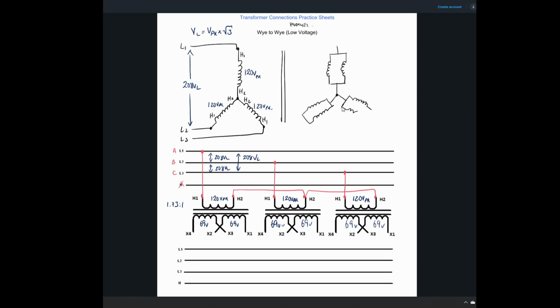I've seen them on solar panel installs where the solar panel output is 277/480 and they want to change that to 120/208, so they'll use a Y to Y transformer. In some machinery or in some installs, you will see a Y to Y connection. The issue with Y to Y transformers, from what I've read, is that harmonics can pass between the primary and secondaries because they have that common connection on the neutral. Sometimes, from what I understand, the primary and the secondary are bonded to ground, so you can have harmonics passing through these units.